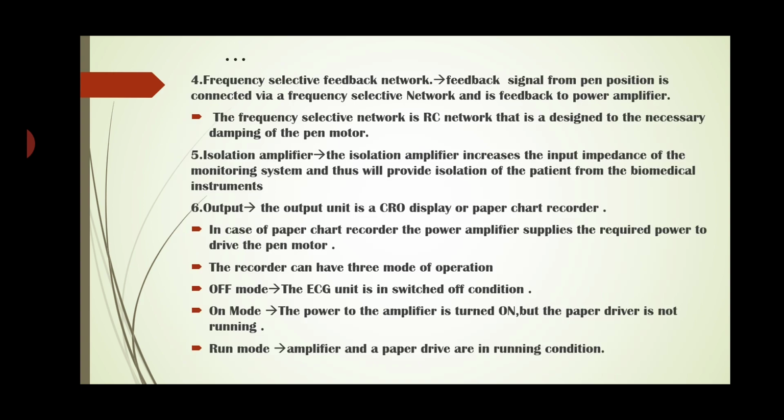The recorder has three operation modes. First is the off mode. The ECG unit is in switched off condition, meaning both the chart recorder and amplifiers are in off condition. Second, on mode: the power to the amplifier is turned on, but the paper drive is not running. Third, run mode: amplifier and paper drive are in running condition. So these are the three modes in the operation of a recorder.